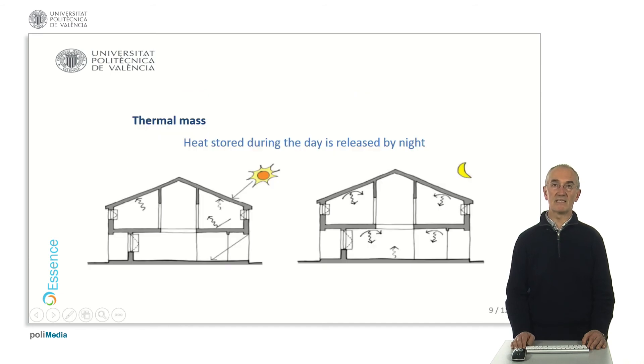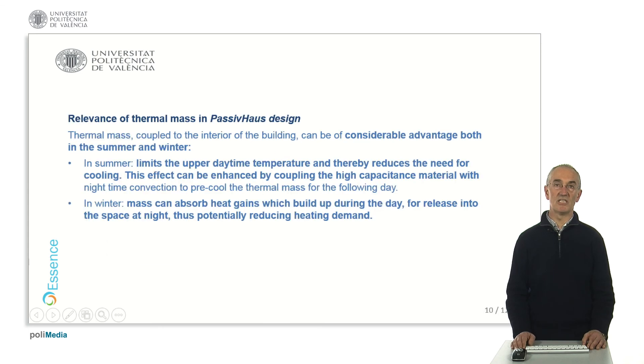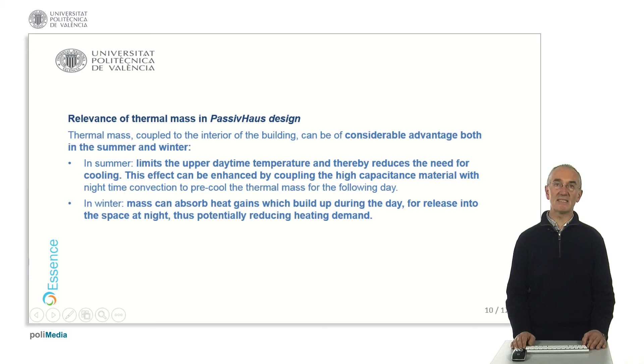Next comes thermal mass. We need in some cases to store energy — either heat to be released by night, or the other way around: to absorb as much energy as possible in order not to have an extremely hot atmosphere during summer. Thermal mass is especially relevant where it is facing the sun and where it suffers most from outside conditions. We must position it as adequately as possible, moving air through that thermal mass for energy accumulation as needed — delivering heat by night during winter or storing heat during the day in summer. We can change the overall storage of energy by using phase-changing materials or by storing as much energy as possible, such as putting water within the walls.